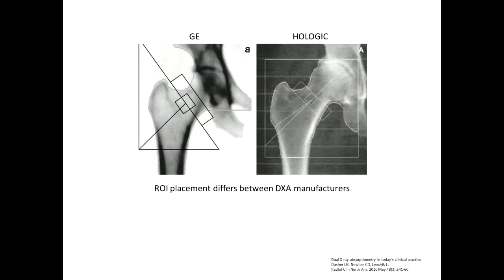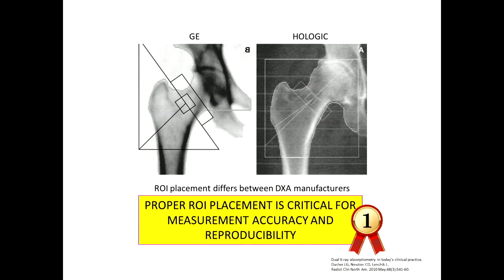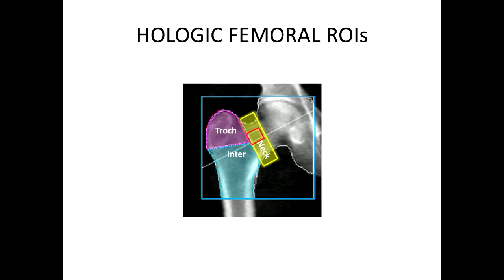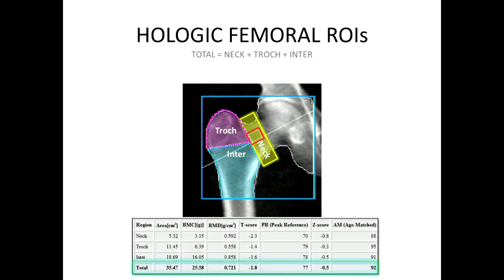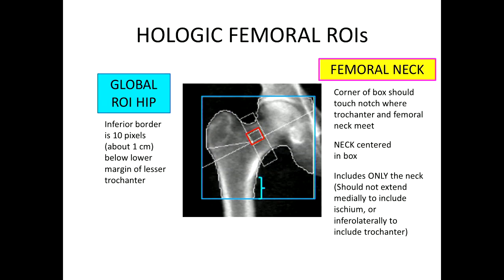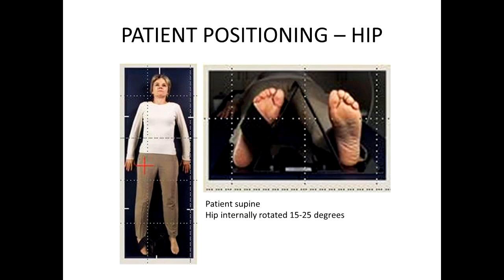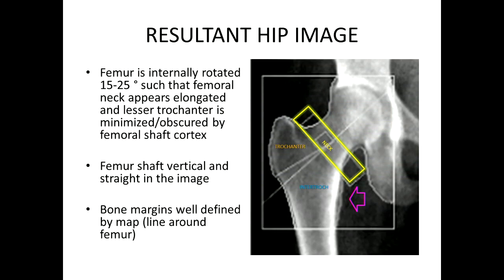While ROI placement may differ between DEXA manufacturers, proper and consistent ROI placement is critical for measurement accuracy and reproducibility. For the Hologic-based system, femoral ROI placement includes the femoral neck, trochanter, and intertrochanteric measurements to give the total. The inferior edge of the global ROI box should lie one centimeter below the lesser trochanter. The femoral neck box corner should touch the junction between the trochanter and upper outer femoral neck, and must only contain the femoral neck centered in this box. The patient must also be positioned with the hip internally rotated 15 to 25 degrees such that the lesser trochanter is barely seen, the femoral shaft is vertical and straight, and the bone margin is well defined by the bone map.